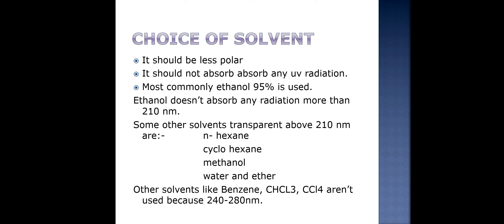The next topic is the choice of solvent — which solvent should be used when operating the UV visible spectrophotometer. The sample solvent should be less polar and should not absorb any UV radiation. The most commonly used solvent is ethanol, which is 95% pure, because ethanol doesn't absorb radiation above 210 nm. Other solvents transparent above 210 nm include N-hexane, cyclohexane, methanol, water, and ether. Solvents like benzene, chloroform, and carbon tetrachloride are not used because they absorb in the 240 to 280 nm range.